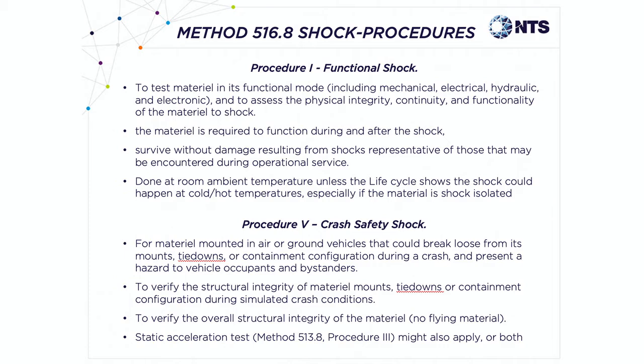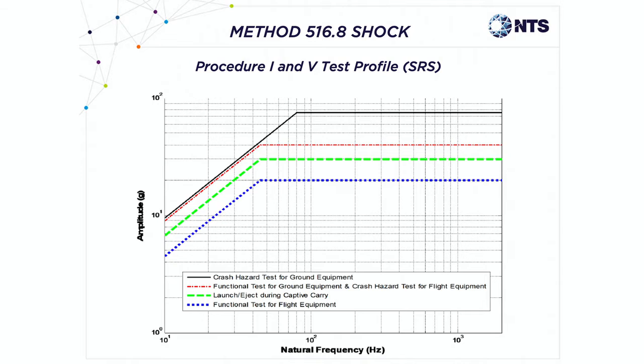Now, the shock response spectrum is just what it is. It's a response to a shock input. We'll design a drive wave, input it into the shaker, and hit the spectrum. It's done at 1/12th octave intervals, but there are some limitations on the time history. The time history is the drive wave we put into the shaker to produce this shock response.